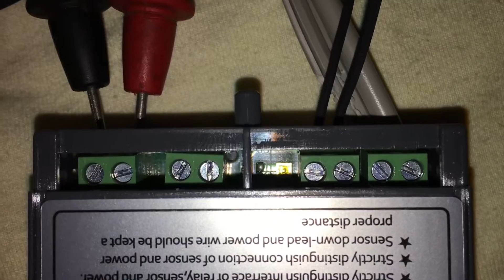But this is kind of nice, you know - when you take that little cover off, it's just held on by one little screw. You can troubleshoot that way, check your power, but I don't recommend it. You need to take the sensor wires out. You could check for an open or a short just right here, but if you want to actually ohm the sensor out, you need to remove at least one wire to ohm out the wire.